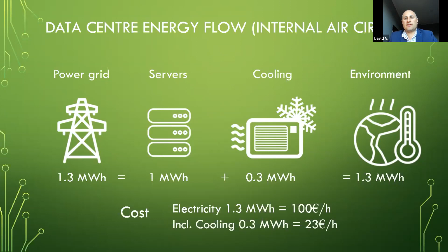Let's evaluate how energy goes in the data center where there is closed loop air circulation. You get from the grid 1.3 megawatt to provide 1 megawatt for the IT load and 0.3 megawatt for the cooling. And all that energy is transferred to heat rejection - there is no way to hide the energy. It's all transferred to the environment, to the ambient air. The cost of electricity for 1.3 megawatt is 100 euros per hour. Among them, for cooling, is 23 euros per hour. These figures are just to understand what the cost is.